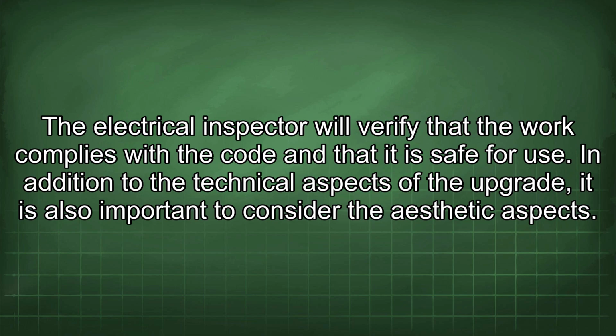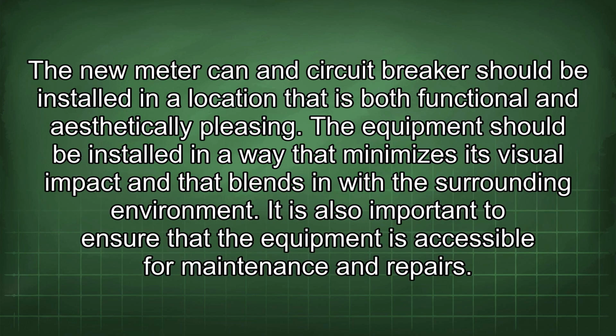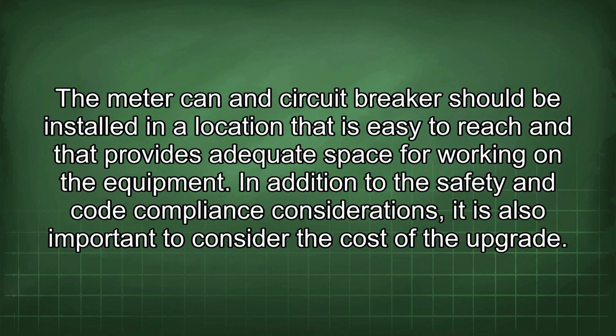safe for use. In addition to the technical aspects of the upgrade, it is also important to consider the aesthetic aspects. The new meter can and circuit breaker should be installed in a location that is both functional and aesthetically pleasing. The equipment should be installed in a way that minimizes its visual impact and that blends in with the surrounding environment. It is also important to ensure that the equipment is accessible for maintenance and repairs. The meter can and circuit breaker should be installed in a location that is easy to reach and that provides adequate space for working on the equipment.